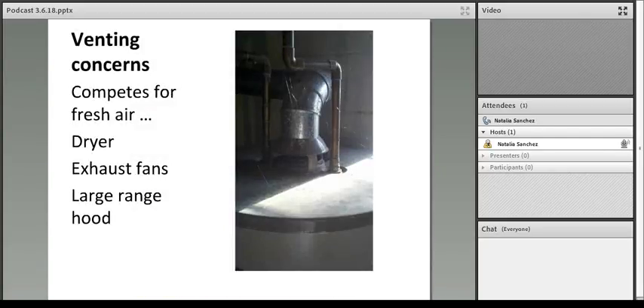And then the other part of heating and cooling is water heating, and here's the water heater. This is a low efficiency water heater. It's known as atmospheric venting. And the reason why I'm bringing it up is that these are really critical to make sure I don't create spillage, because that vent path can be influenced by very small pressure changes in the house. This venting system competes for fresh air with the dryer, exhaust fans, and range hoods, and they easily distort the flow path, and we call it spillage. So any products of combustion from the water heater are going to come into the living space. We generally don't want that.